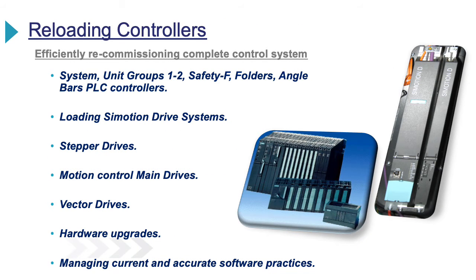As a technician, you will have to know where the software is located for backups and how to reinstall the software to get the systems up and running quickly, and how to replace the component failures and make sure that they are commissioned properly. All these need to be done in the system, the unit PLCs, drive controllers, redundant safety PLCs, frequency drives, stepper drives, and communication modules.